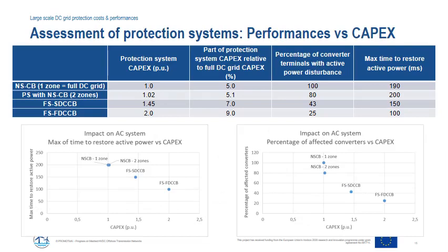These two graphs present the two considered performance indicators versus the cost of the protection system for the four considered protection strategies. It can be observed that higher performance is obtained with a fully selective strategy with a fast DC circuit breaker, but at up to twice the cost of the non-selective with converter breaker strategy. The grid splitting concept seems to allow for an increase in performance at quite a low additional cost when implementing non-selective fault clearing strategies.